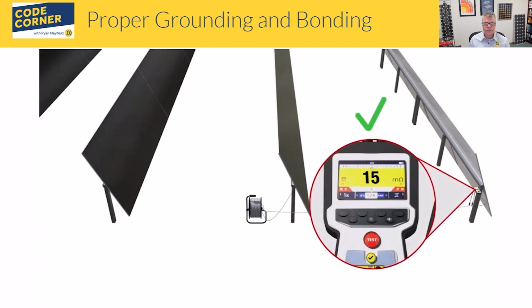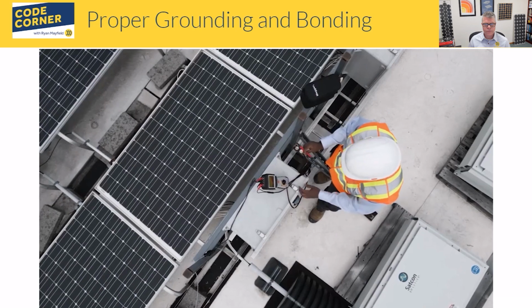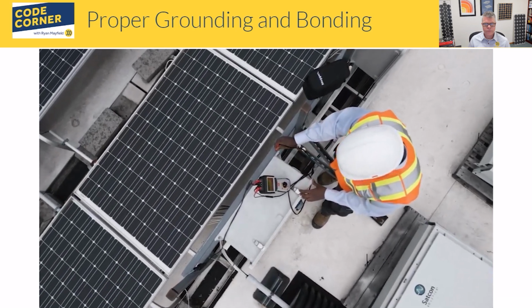Resistance values in the milliohms are expected. Any values greater than 10 ohms should be investigated. Repeat the test by moving the probe to a different metallic component. Record all measurements.